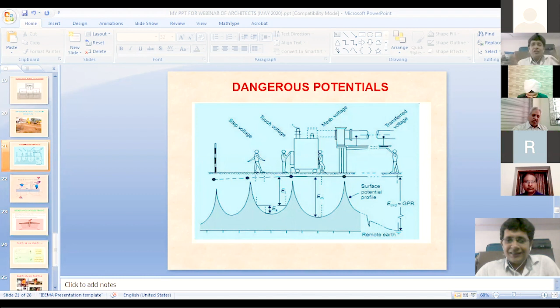These are the dangerous potentials that occur everywhere when there is a fault: step potential, touch potential, mesh potential, transfer potential, and GPR. We have to take care of these. These pictures depict step potential when there is a fault. When you start moving, there is some potential difference between your two steps, and when you start touching anything, touch potential happens. That must be within the safe limit, otherwise you are going to get a shock.